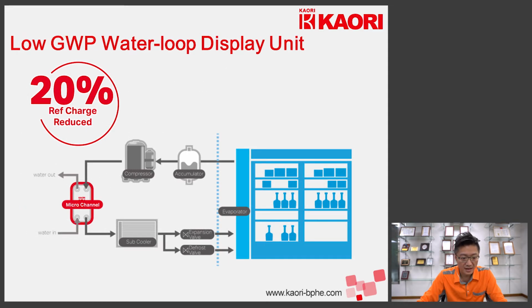And in this slide, here is an example of a low global warming potential water loop display unit. By adopting a microchannel condenser, we are able to save 20% of the refrigerant charge. This is perfectly suitable for smaller scale showcase with R290 propane.